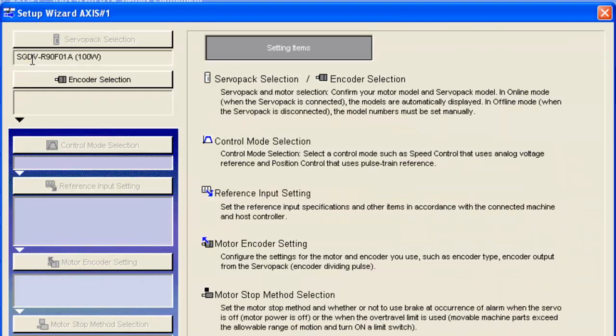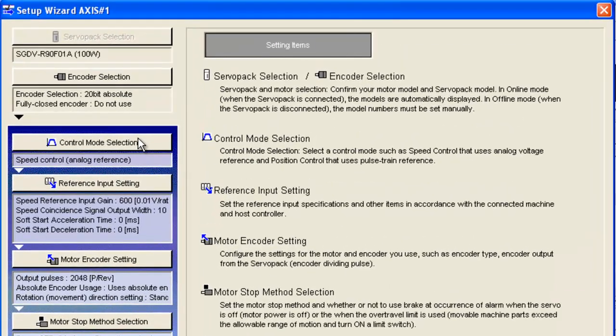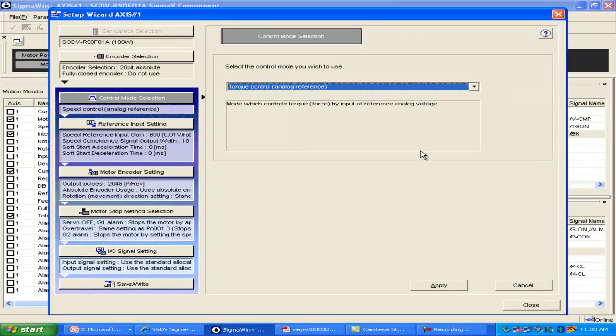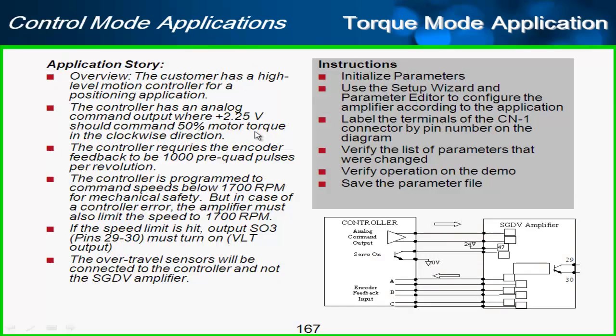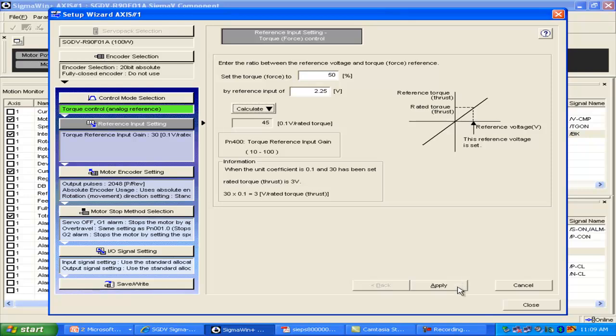I'll hit encoder selection. I'm not using the fully closed encoder, and we'll start with the control mode. We know from this setup that we're going to be commanding torque, so I'll choose torque control mode and hit Apply. Next is the reference setting, where it says 2.25 volts commands 50% torque — I can enter that in here. Then hit Calculate and Apply.